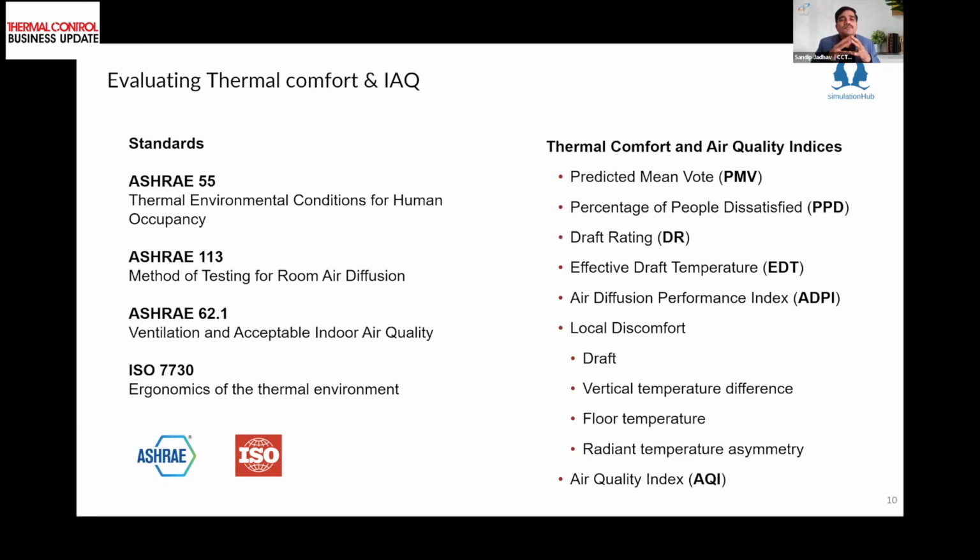And then it also comes up with local discomfort parameters, which are very helpful. These are basically the draft effect, vertical temperature difference, floor temperature difference, and radiant temperature asymmetry.